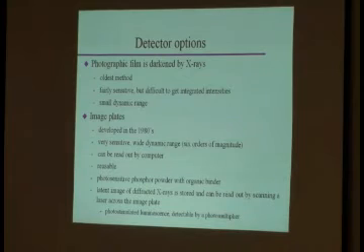In the 80s, people developed image plates, which are actually fairly similar to film, okay, but a lot more powerful. They are much more sensitive. They have a very wide dynamic range, as a matter of fact about 6 orders of magnitude, so that's pretty good. They can be reused in contrast to film, so that's certainly an advantage. You can read them out with a computer. Ooh, now that's good, right?